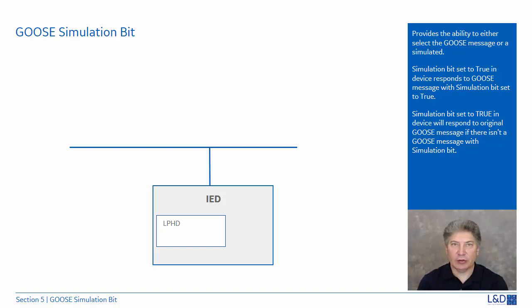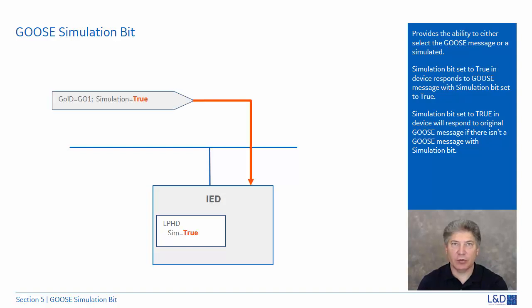The LPHD logical node has the data object defining whether the IED will be accepting real or simulated data. If the LPHD sim object is set to true, it will accept signals with the simulation bit set to true as well. If the LPHD sim object is set to false, it will accept only real signals, where the simulation bit is set to false. Let's take a look at how the different types of signals are handled.